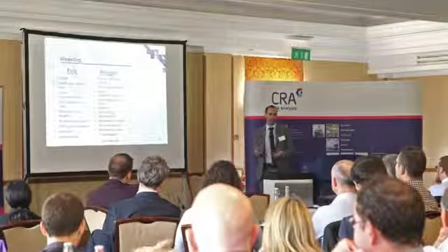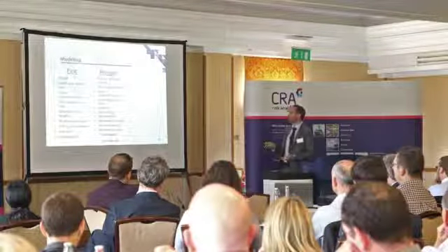I think the key thing is that if you have a deterministic assessment that's nice, done at the time where you're building the plant, and you say, yeah, this will definitely take this level of earthquake. You do one or not on your PSA, you don't see cut sets, you keep going on. Now, PSA is not the main driver, and I think in the UK we generally are quite good at redoing assessments anyway. But if you've not got seismic cut sets coming up and keep telling you if it's still a problem, still not, in the context of your PSA, I think there is a danger that you're not going to go back to your deterministic assessment and say, hang on a minute, is this really true? And as a result, things might not get updated.